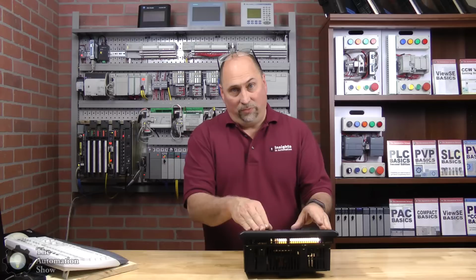that PanelView is the Ethernet version. Now, I tried to corroborate this using both Rockwell's website and the manuals, and I couldn't find anything on it. There may be some tech notes behind the paywall that I don't have access to that talk about this more in depth, but none of the public ones did, and the manual didn't either. The help file did make it sound like it was possible, and I did try it, but it didn't work. I could not use tags as addresses, like Tag_A[0], in lieu of something like N7:0. I just could not get it to work.